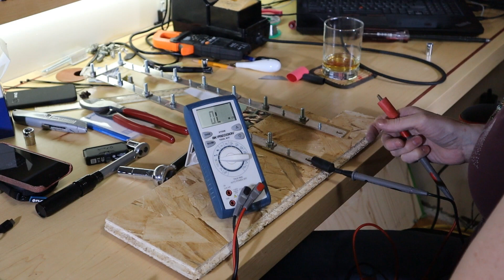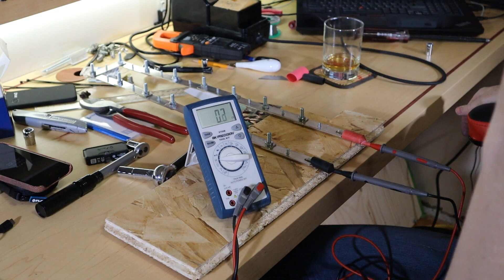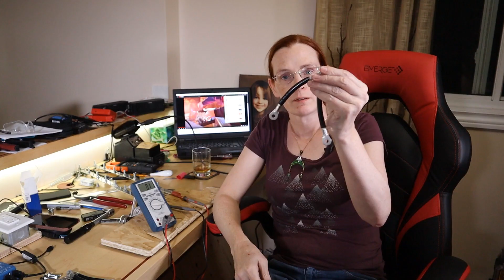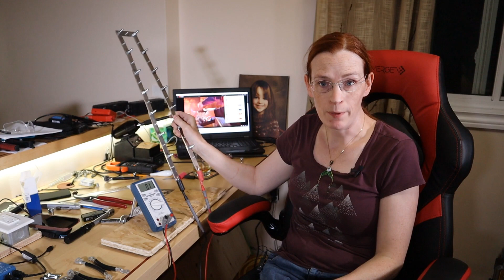So the settled resistance was 0.1 on the chain of flexible bus bars. And we have 0.2, 0.1. Fifteen of the jumper cables that I made, strung together, measured 0.1 ohms of resistance. And the 15 rigid bus bars also measure 0.1 ohms of resistance.